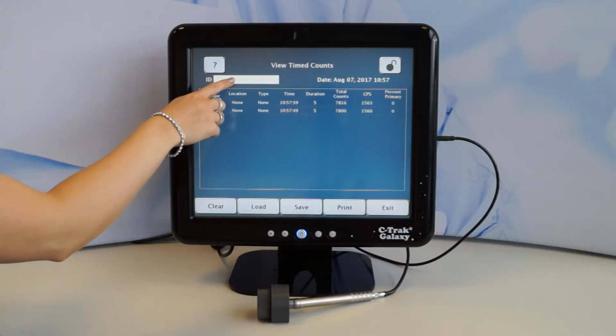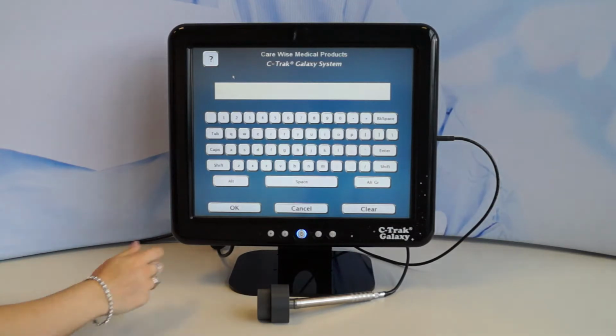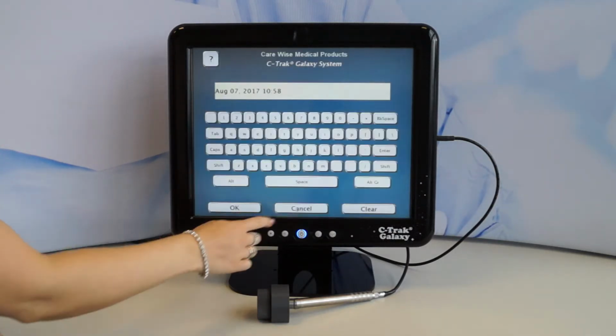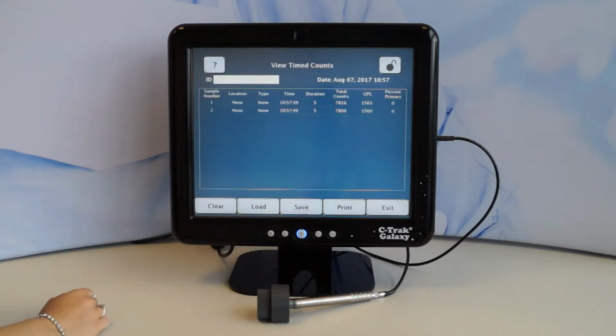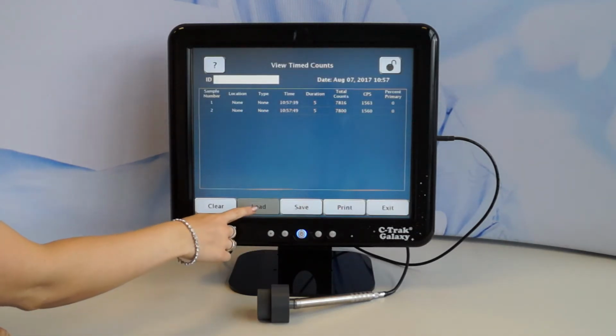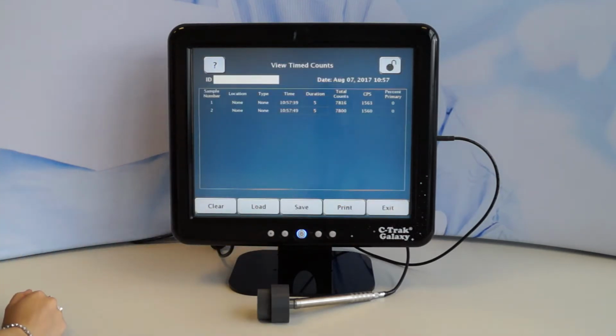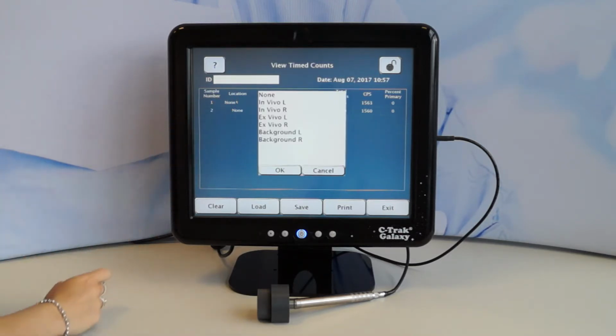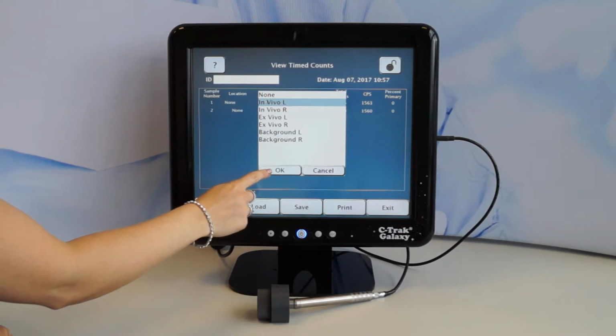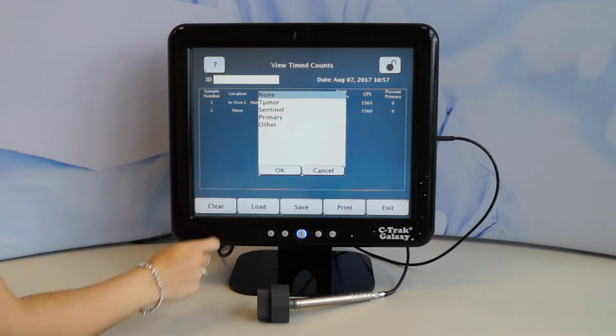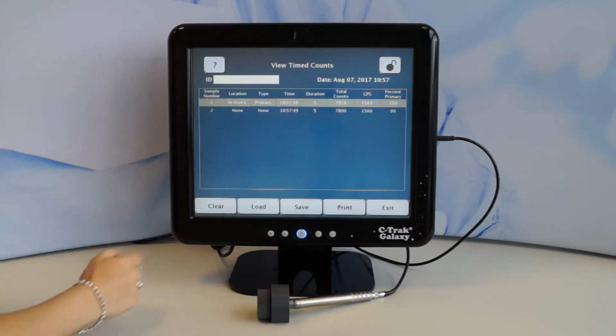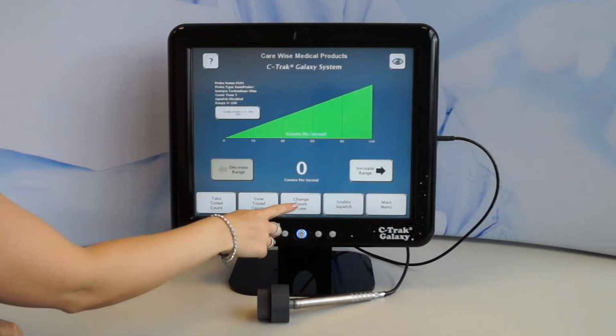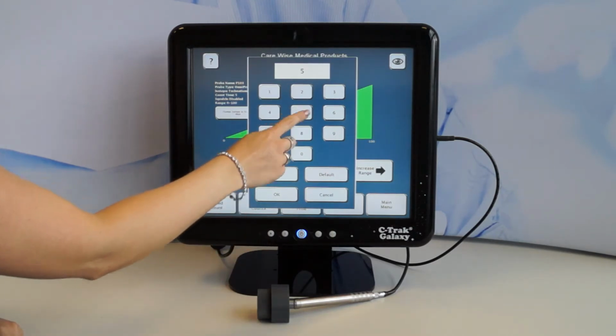From this screen you can input patient name, ID or date and time, and you can save this data to retrieve at a later date or print if you have the printer option. You can also load previous saved counts data. If you do not save, the counts will be lost when you turn the system off and on again. On this screen, you can also label the counts location and type by clicking on the associated column. You can choose in vivo, ex vivo and background left or right for location, and tumour, sentinel, primary or other for type. This button allows you to change the count time from the default 10 seconds to any other specified amount.